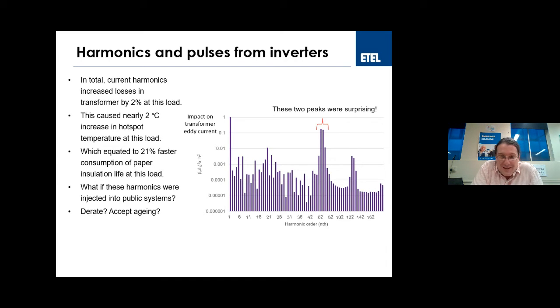Now, the y-axis of that is just the impact on the transformer eddy currents. All this is, is a source of heat. For the first harmonic order we got a value of 1, which is the very left-hand bar. This is showing, under normal usage, how much heat is being dissipated by the transformer. We found when looking at the harmonic content that there were 2 peaks which together were about a third extra heat energy in these eddy currents, which would make the transformer a couple of degrees warmer, and would then reduce its life slightly.